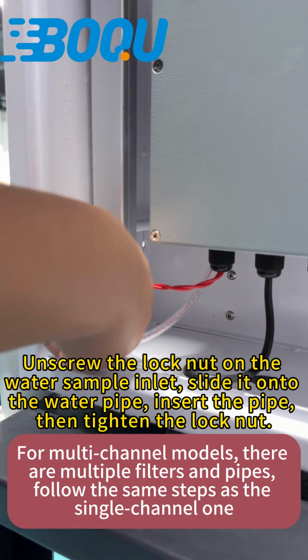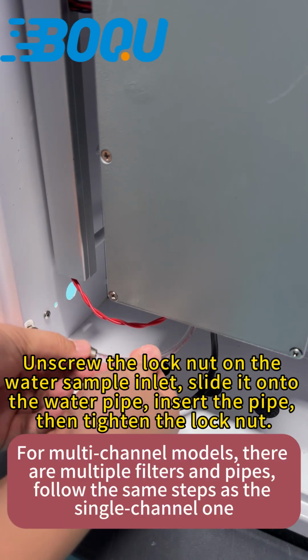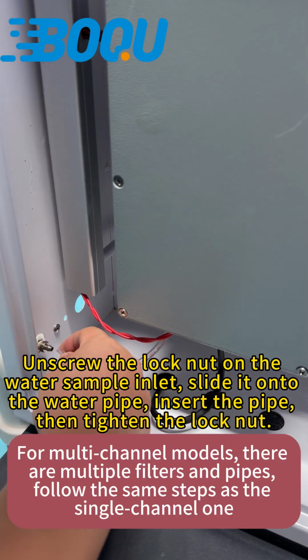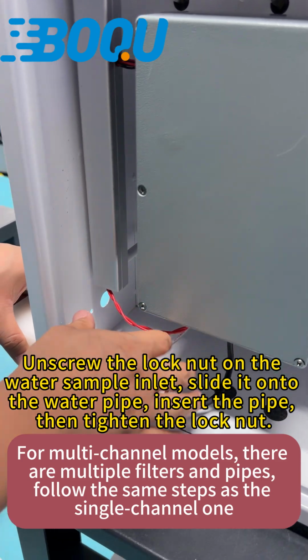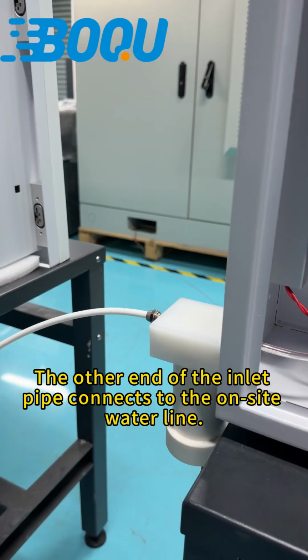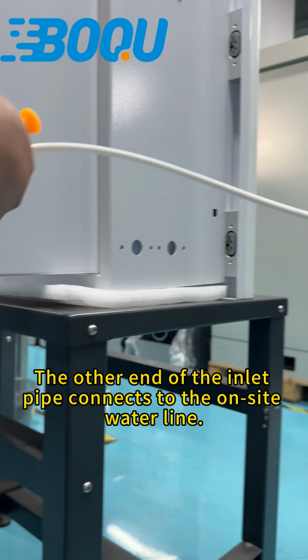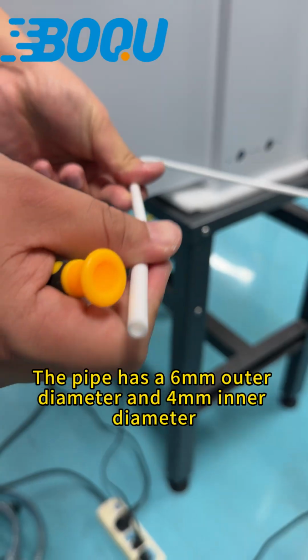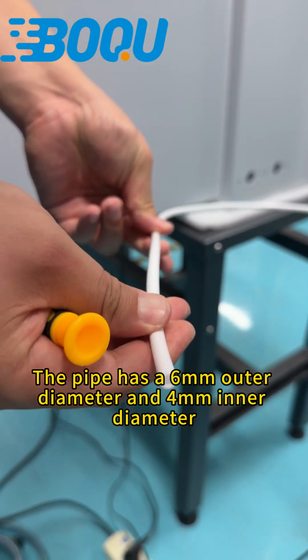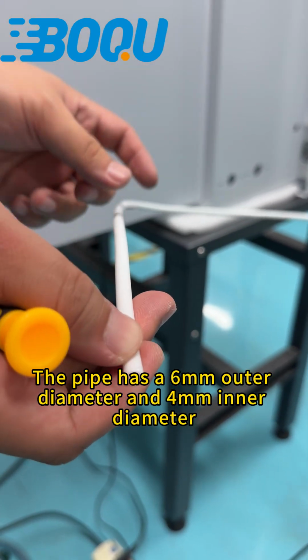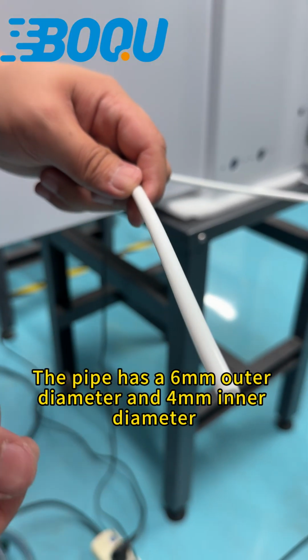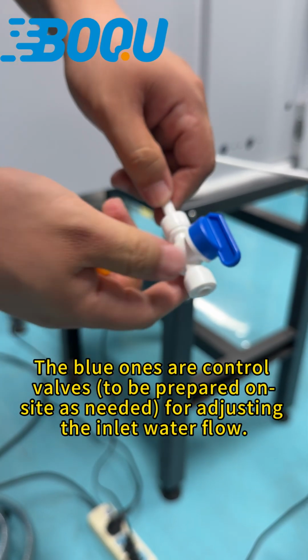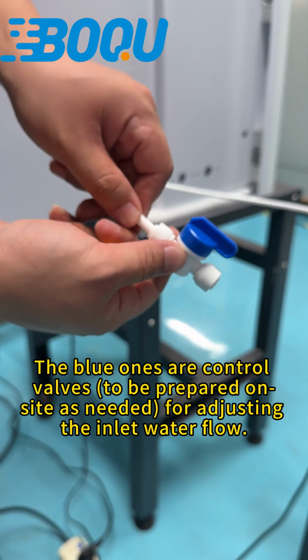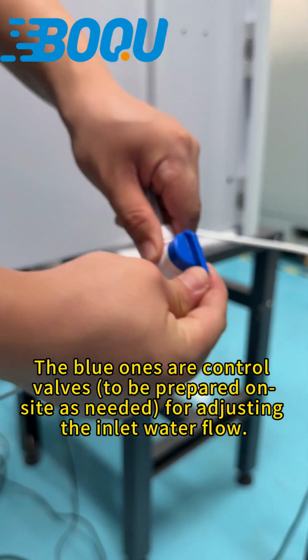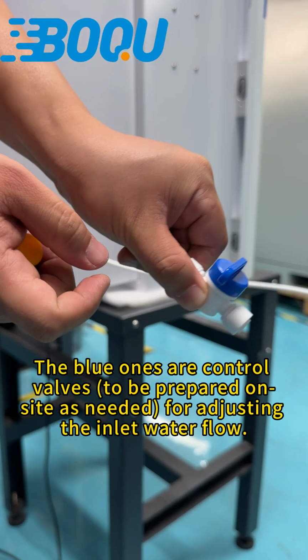Unscrew the lock nut on the water sample inlet. Slide it onto the water pipe. Insert the pipe, then tighten the lock nut. The other end of the inlet pipe connects to the on-site water line. The pipe has a 6 mm outer diameter and 4 mm inner diameter. The blue ones are control valves to be prepared on site as needed for adjusting the inlet water flow.